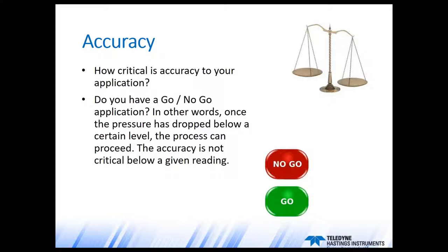The range selection is going to be very dependent upon number two on our list, which is accuracy. Higher accuracy vacuum gauges are generally going to cost more, so you want to ask yourself: how critical is accuracy to the application? For some applications, vacuum measurement is a matter of go/no-go — once the system has gone below a certain pressure, the process can begin. In these cases, accuracy below that level is not really critical.